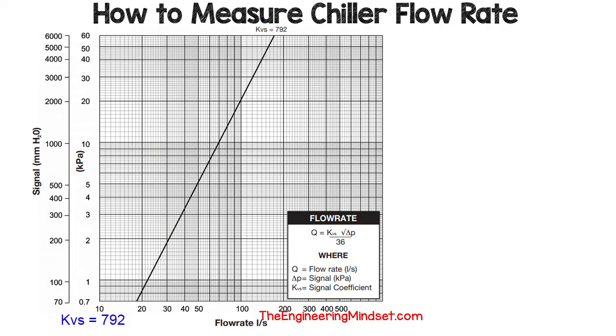Now we can calculate the flow rate. To do this we first need to know the KVS value, which is set by the manufacturer of the orifice plate. The KVS value will vary between manufacturers, model numbers, and also the size of the orifice plate, so make sure you use the correct value.